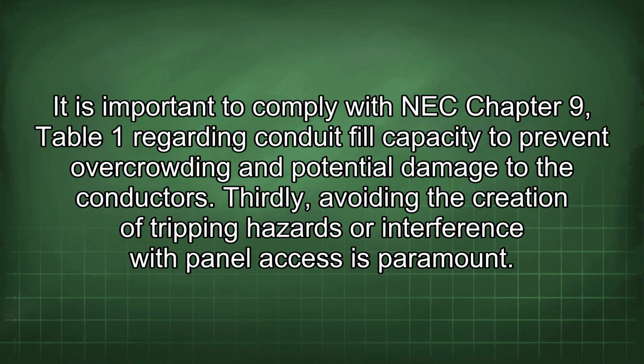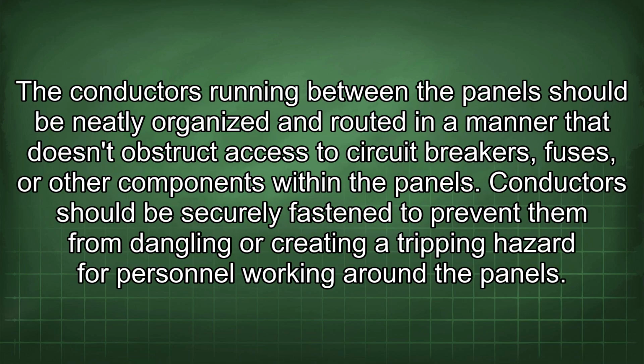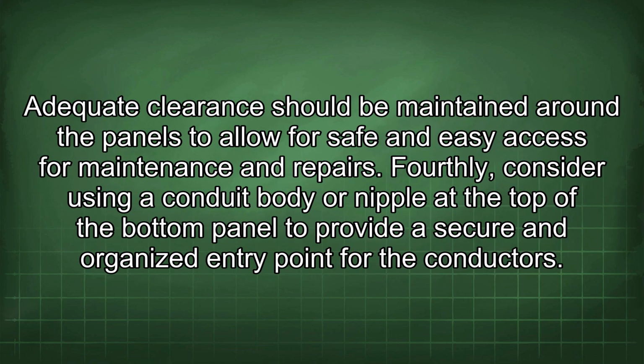damage to the conductors. Thirdly, avoiding the creation of tripping hazards or interference with panel access is paramount. The conductors running between the panels should be neatly organized and routed in a manner that doesn't obstruct access to circuit breakers, fuses, or other components within the panels. Conductors should be securely fastened to prevent them from dangling or creating a tripping hazard for personnel working around the panels. Adequate clearance should be maintained around the panels to allow for safe and easy access for maintenance and repairs.